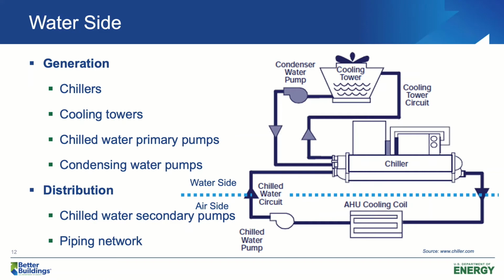We just talked about the equipment on the air side. Now let's talk about the water side. On the water side, we have some equipment for chilled water generation and some for chilled water distribution. For chilled water generation, we have chillers, cooling towers, chilled water primary pumps, and condensing water pumps. For chilled water distribution, we have chilled water secondary pumps and the whole piping network.